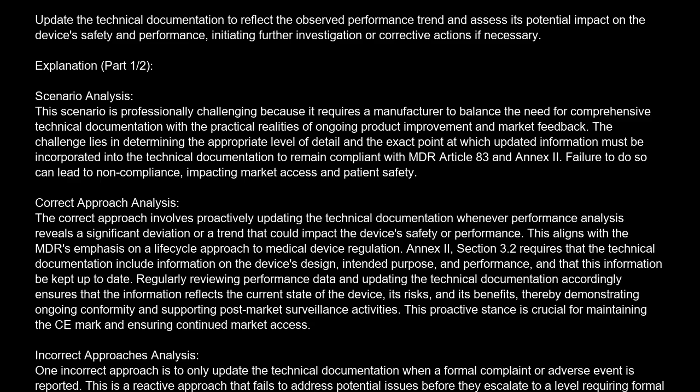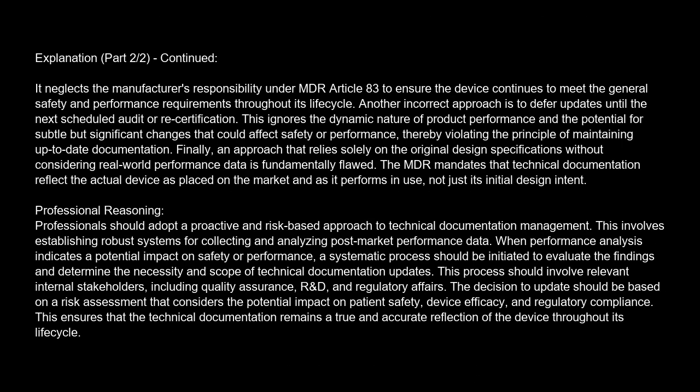Incorrect approaches analysis. One incorrect approach is to only update the technical documentation when a formal complaint or adverse event is reported. This is a reactive approach that fails to address potential issues before they escalate to a level requiring formal reporting. It neglects the manufacturer's responsibility under MDR Article 83 to ensure the device continues to meet the general safety and performance requirements throughout its life cycle.